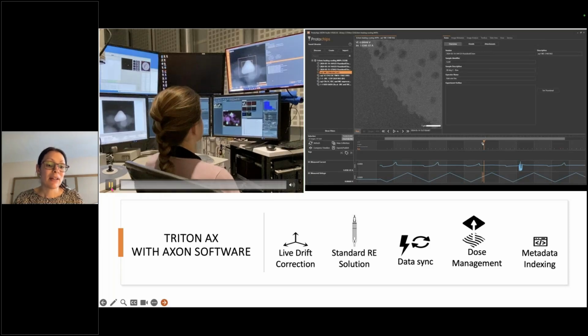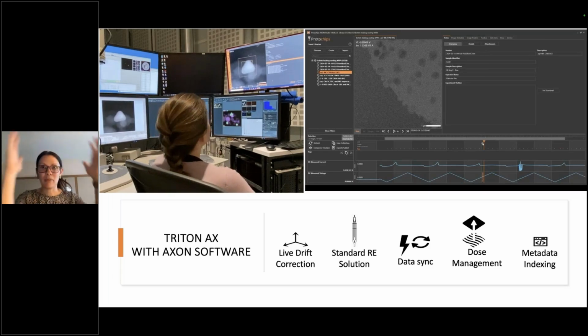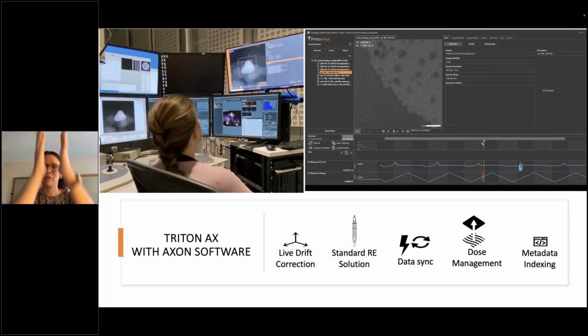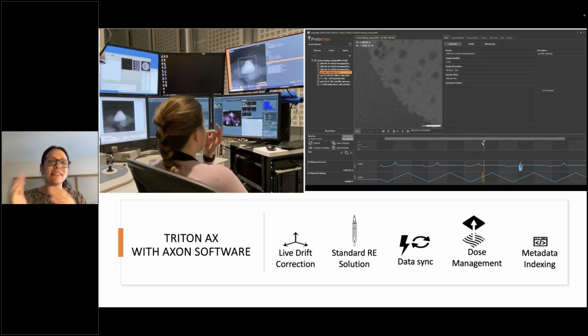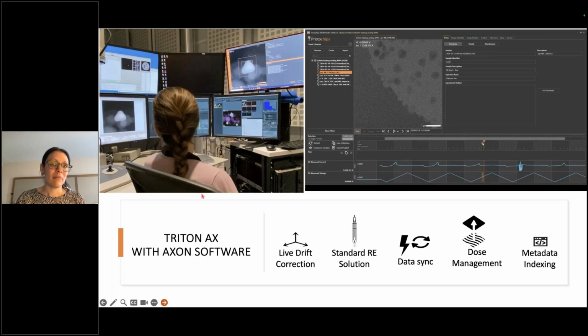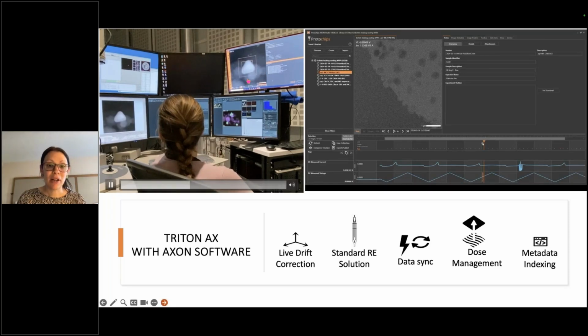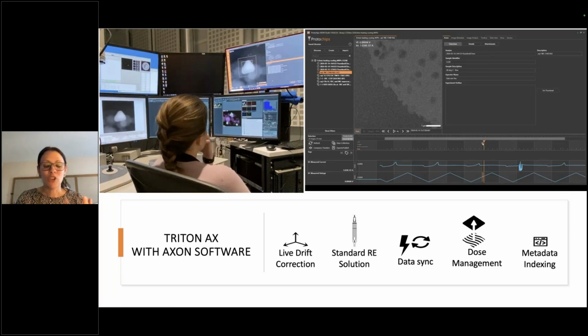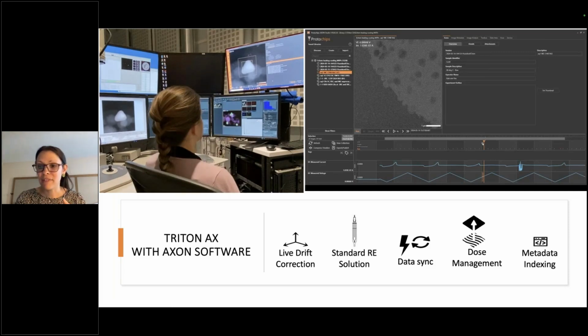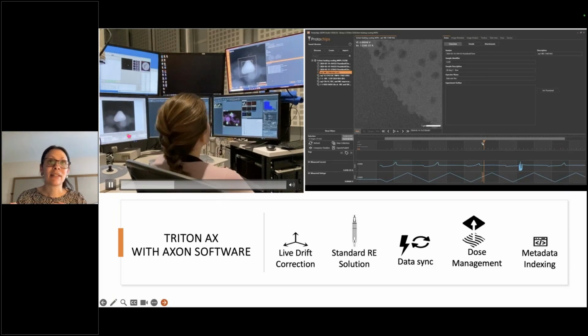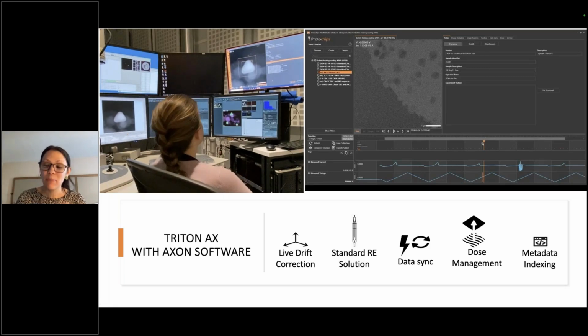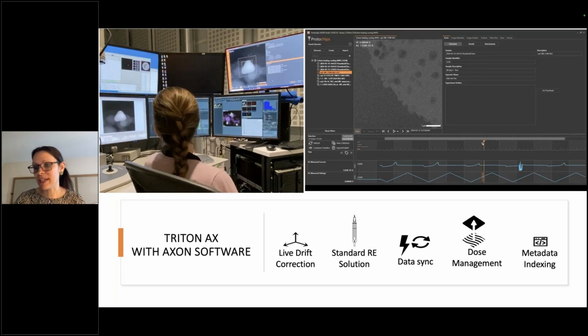An example here is the Triton synchronicity software. If you remember from my map, the synchronicity software was in the lab with you, and it was a long bar in my product map. It's communicating with the TEM and with the in situ software so that you, as the microscopist, can sit here and observe your experiment, which in this case is a temperature experiment. It's going to do stabilization, note-taking of the parameters as they change, and alignment of all of that with your images for you. It's calibrated to your TEM so that it will sample the images as the experiment is occurring, analyze the movement of the sample itself, and then communicate back to the TEM to physically correct for any drift or any movement that's occurring.